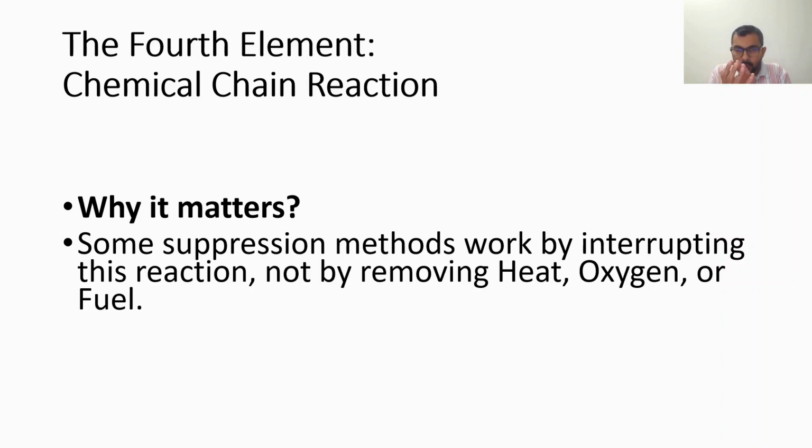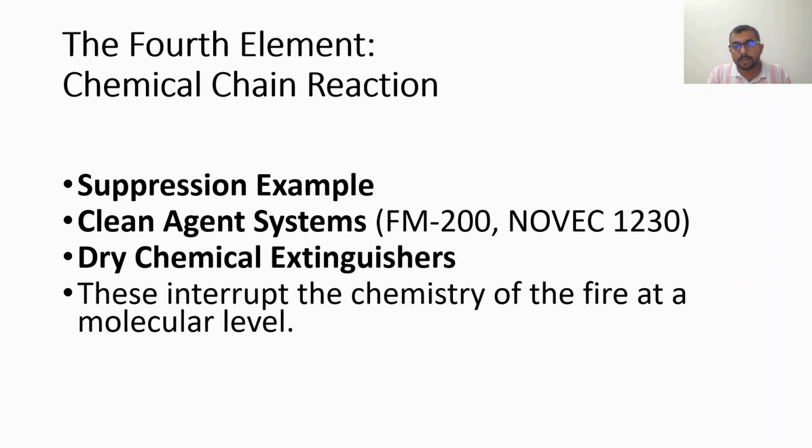So if you remove the heat, the oxygen, or the fuel alone, it might not suppress the fire. In order to suppress it effectively, you need to stop the chemical chain reaction. For this, some of the suppression systems are clean agent systems, normally in the names of FM200 and Novec 1230. Such systems form the clean agent gases.